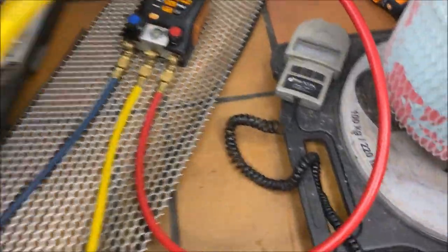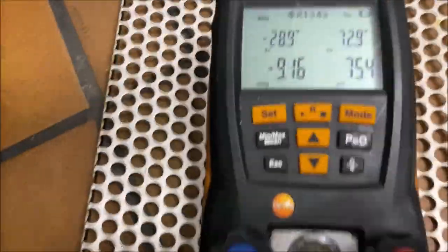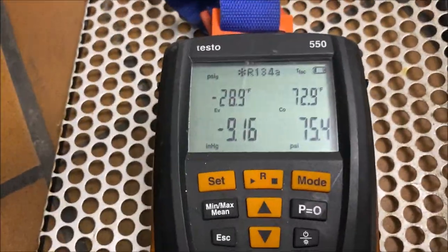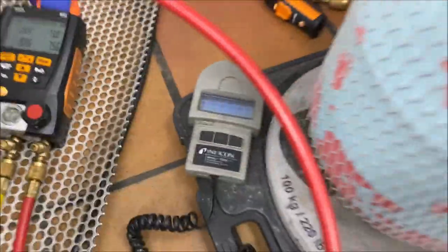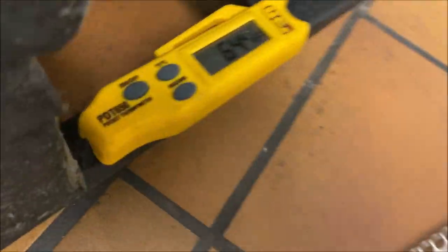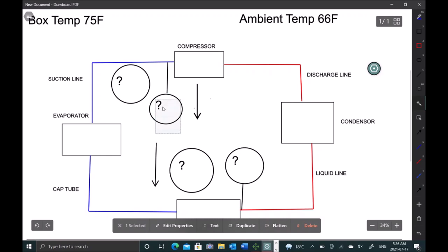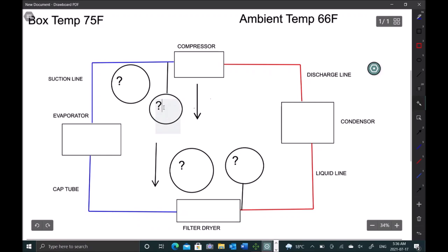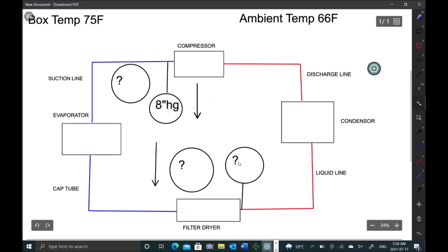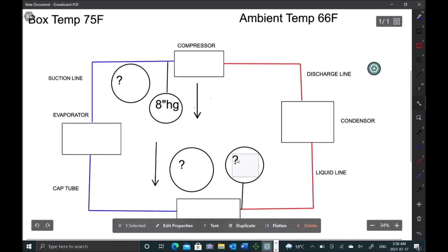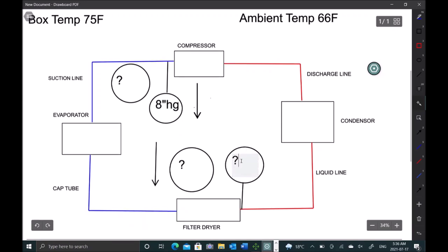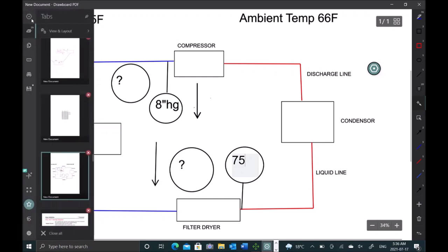All right, so I'm going to gauge up now. So I'm getting about 8 inches mercury, 75 PSI on the head pressure and 65 ambient. All right, so our suction pressure is 8 inches mercury, our head pressure was 75 PSI. So let's go ahead and look at our PT chart and see what we should be getting.